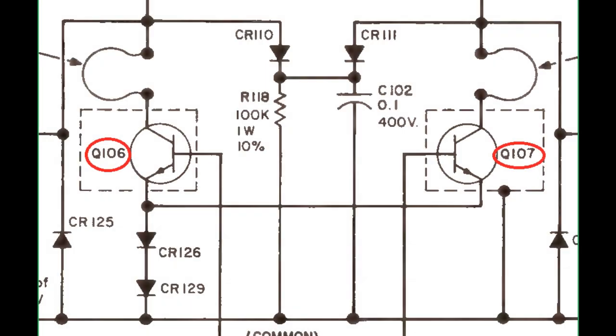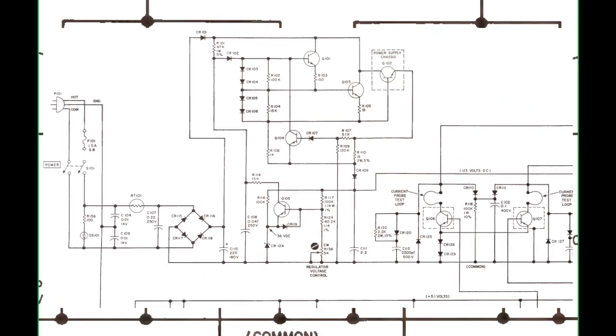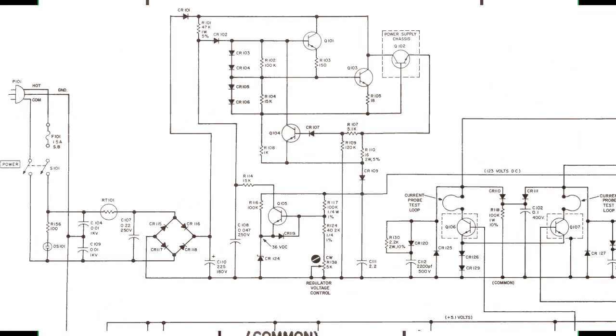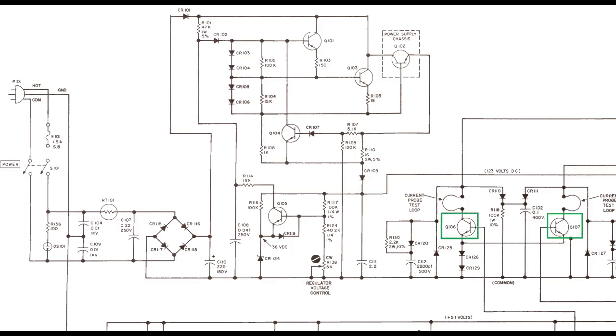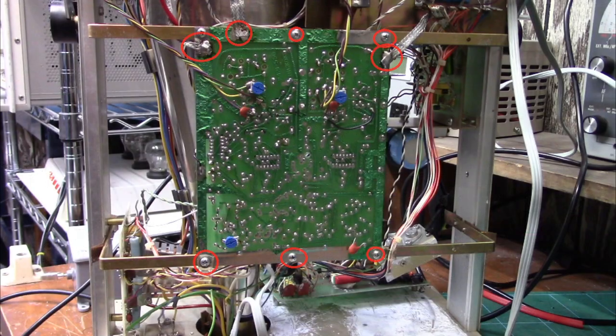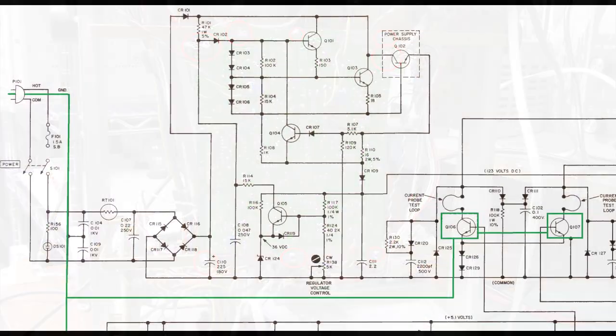My first thought was that I had connected the bracket, and hence the collectors, to the common ground rail. However, when I took a closer look at the schematic, I noticed that the bracket is already connected to common, so that wasn't the source of my short. I had to zoom way out again to see what I did. By not installing those two insulators correctly, I ended up mounting that bracket directly to earth ground. Now there are literally dozens of spots on this scope that are connected to earth ground, so I might have caused a lot of damage.